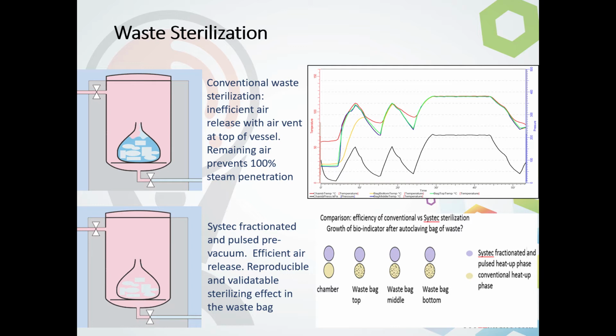If you look at the efficiency of conventional versus a Systec sterilization process, these are tests that we ran ourselves. You can see with the Systec fractionated and pulsed heat up phase, we have completely eliminated all of our biological indicators. They are completely negative. Whereas with the conventional heat up, even in the top of the bag, the middle, or the bottom, we're still not going to actually achieve complete sterilization.